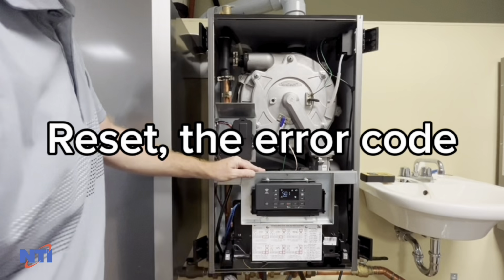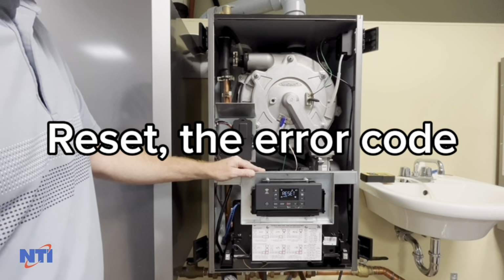A thermostat call may be generated by using a jumper on TT1, a hot water call, or by turning up thermostats. In this video, I am using a jumper wire. Reset the error code before continuing testing. Tap the reset button twice.